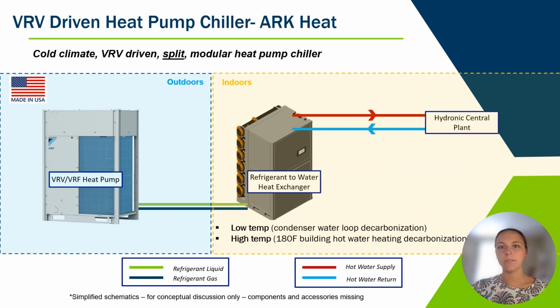And finally, I want to talk about DXS's solution for the industry's first VRV-driven split modular heat pump chiller with ARK Heat. And again, we'll start with our cold climate Daikin VRV condensing units connected with refrigerant lines to these indoor mounted large capacity modular refrigerant to water heat exchangers. And this is what we call the ARK Heat XE units. And we have a similar story here as with the MegaQ domestic hot water solution, where all of our water can be kept inside the building, which again removes the need for glycol or heat trace. And this setup can be used to electrify and maintain condenser water loops for decarbonization, which we're seeing more and more demand for, especially with the recent requirements for building emission reductions in Boston and surrounding areas.